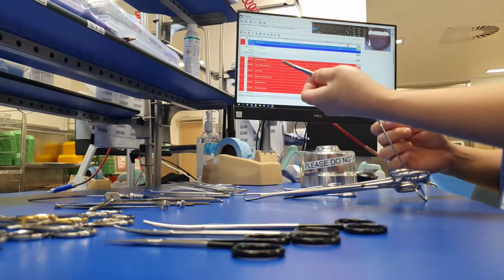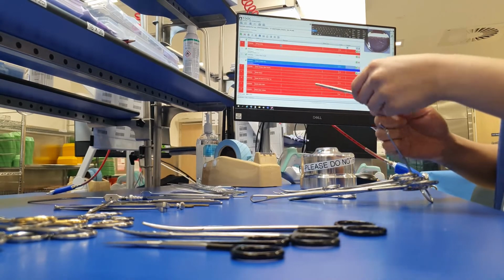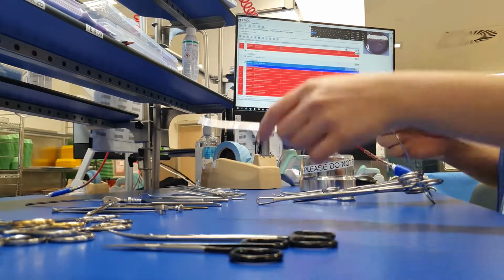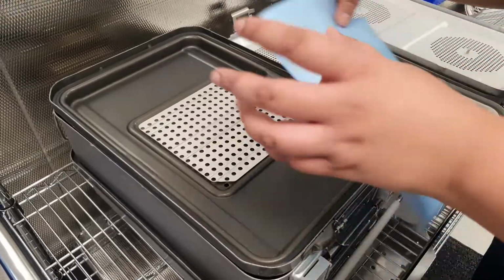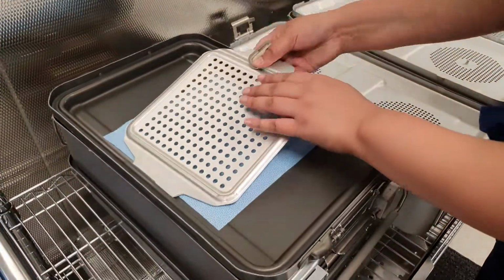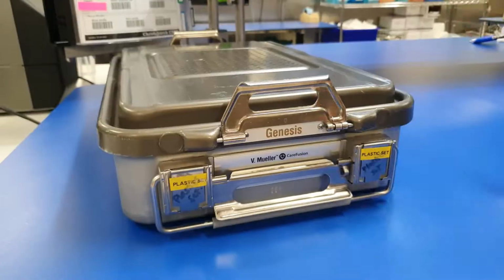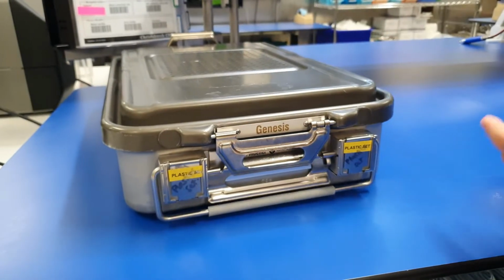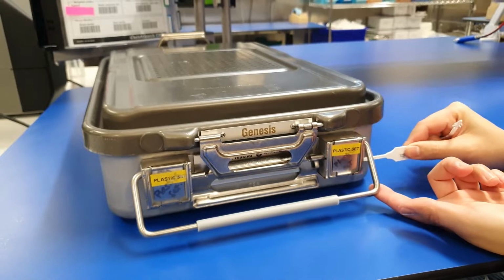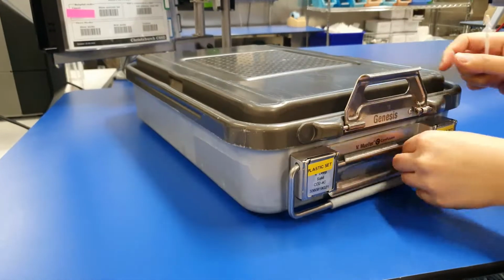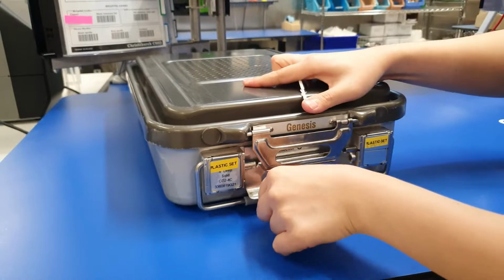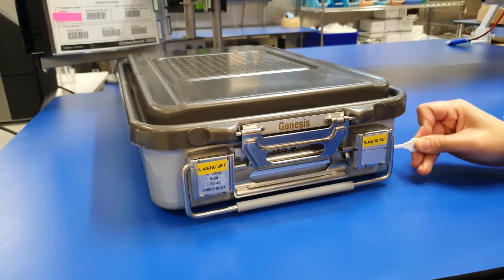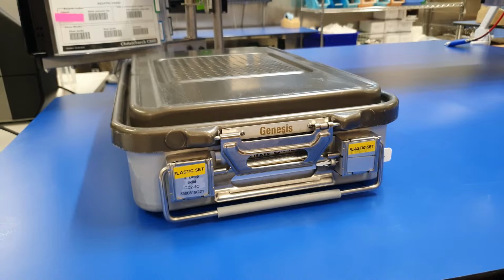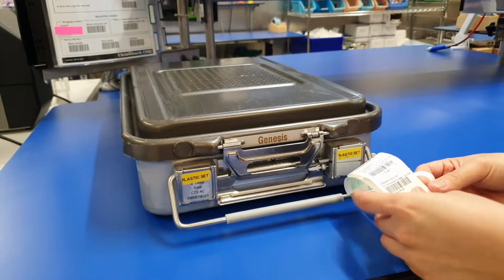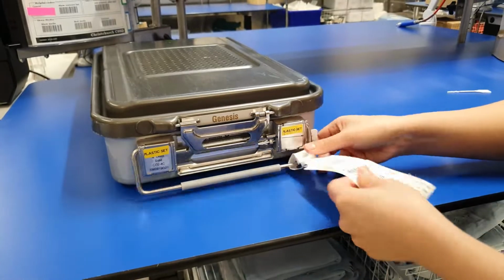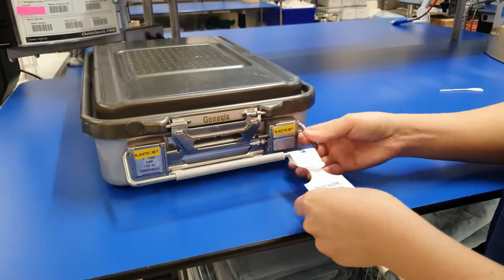We then start scanning the instruments, and once all instruments are inspected and complete, we place the instruments in a crate with a new disposable sterile filter. It is important these filters are positioned correctly during sterilization to allow air movement. We also attach the printed label, which tells you the name of the set, who inspected it, the date and time it was packaged, and other information necessary to track the set. We then close the crate with chemical indicator seals.